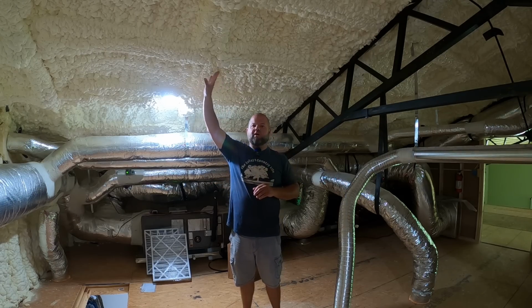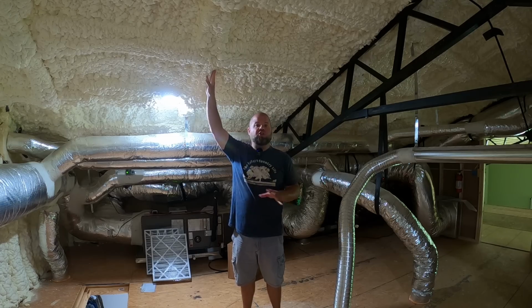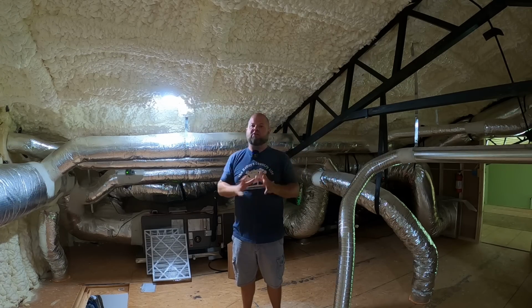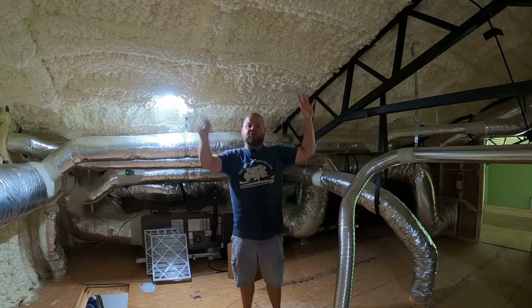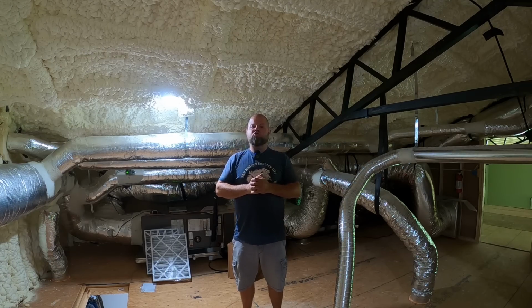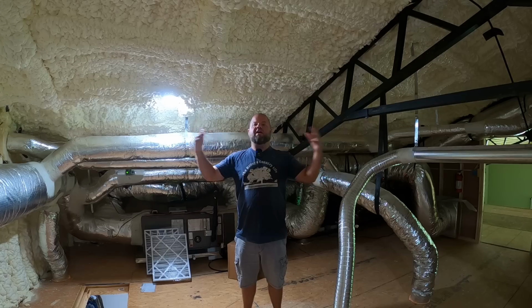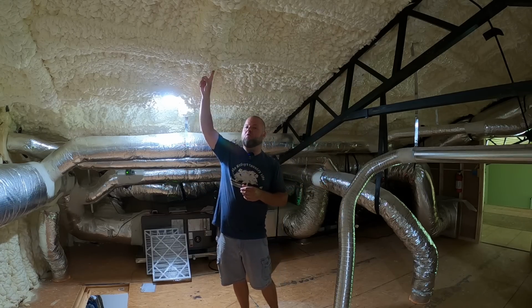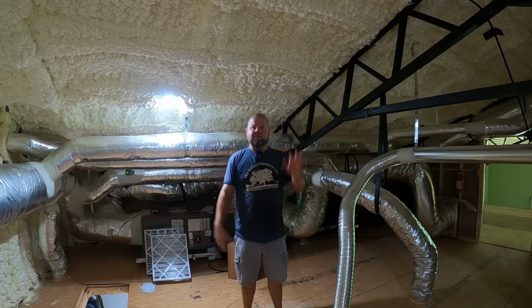Whenever you do this well-sealed of a house, my air changes per hour number, ACH number, was as good as a lot of y'all have ever seen. I sealed this house up as good as I possibly could. Then I paid the insulators to come in and spray foam this, as well as caulk every joint behind me, seal the house up as good as it could possibly be. And I had an extremely low air changes per hour number, which means how much air naturally flows in and out of a home. Because spray foam itself is already such a good sealer, if you spray foam a house, you need to understand that you're not going to turn over air as frequently as a leaky home that has fiberglass insulation and everything else.